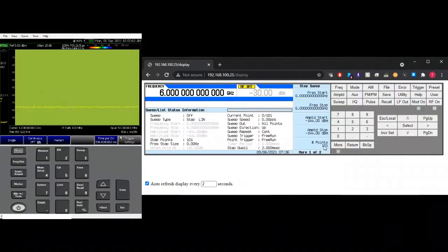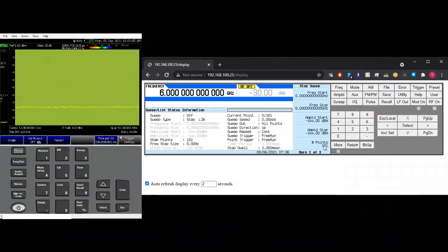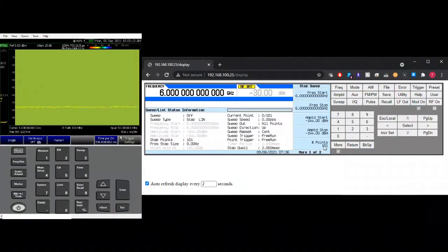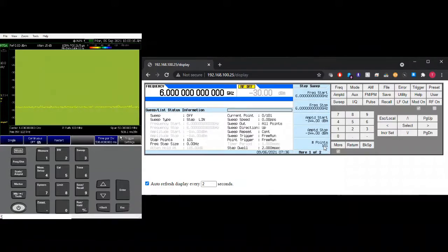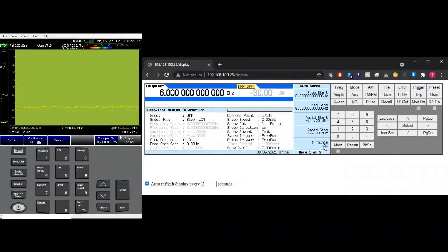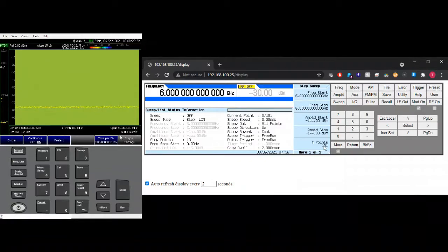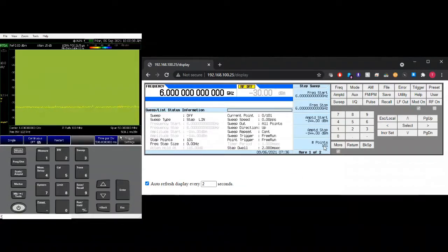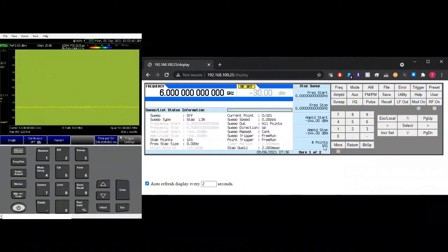Sweep step is useful when you have an equally gap point. Like for example, if you want to sweep between 1 gig to 1.04 gig and then you want to set it to 3 points means that it will step between 1 gig, 1.02 and 1.04. And subsequently if you want to add in more points, you just continue on from there but you just have to set the start and stop frequency and it will be equally divided in between the points. Same for the amplitude.